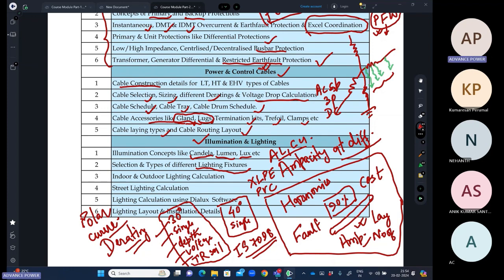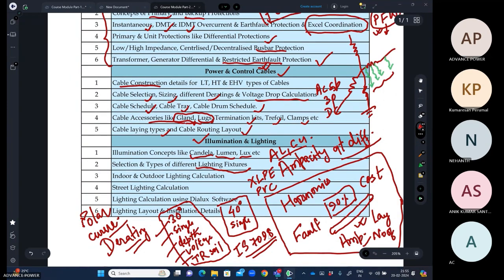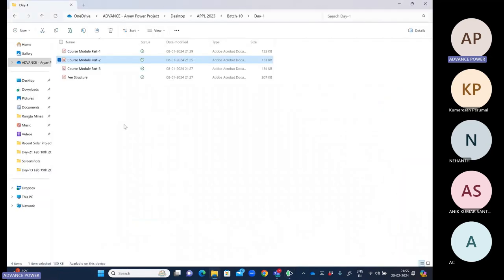Then in the second case, we'll import the AutoCAD file of your substation layout, and on that we'll make a switchgear building and a control room building. We'll do the lighting, and whatever the desired lux level as per IS is required, or as per the specification given by the client, we will design that.